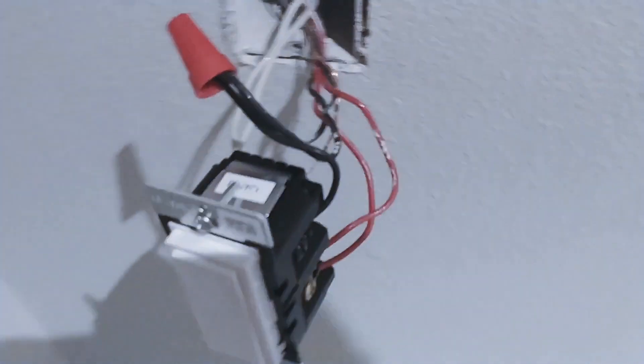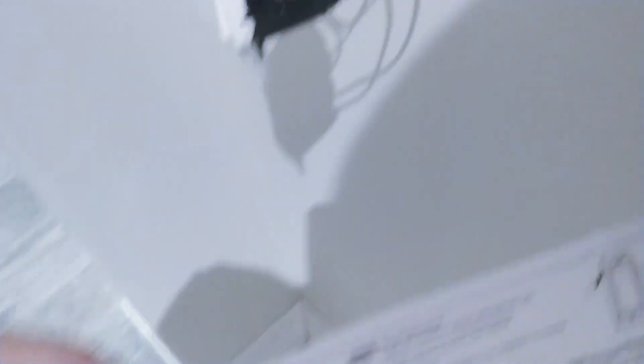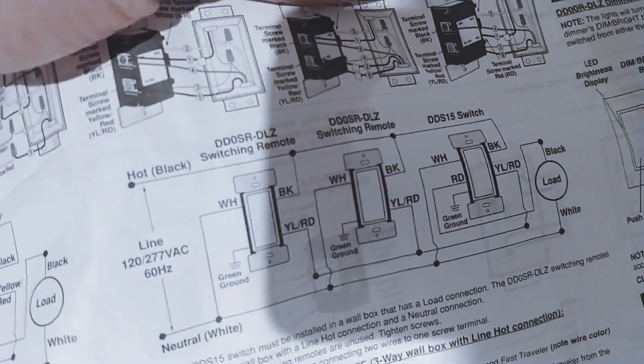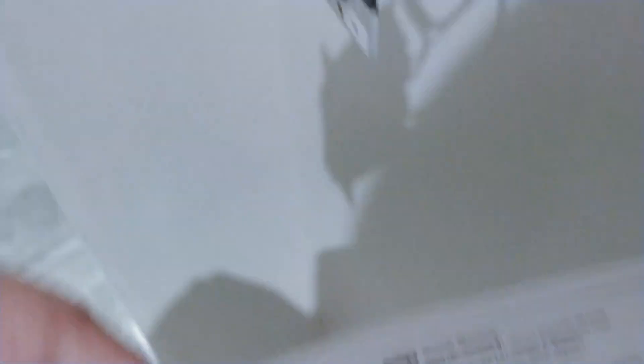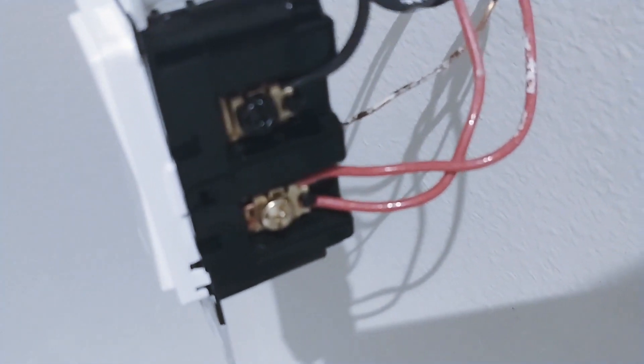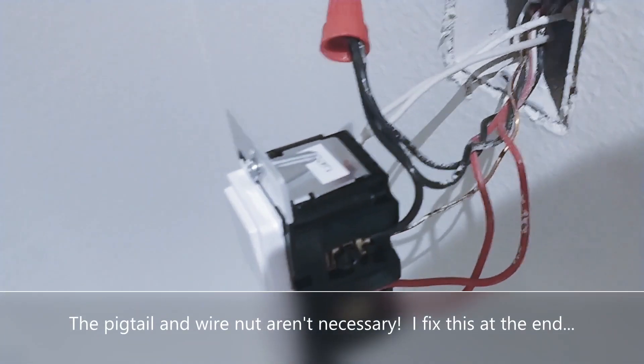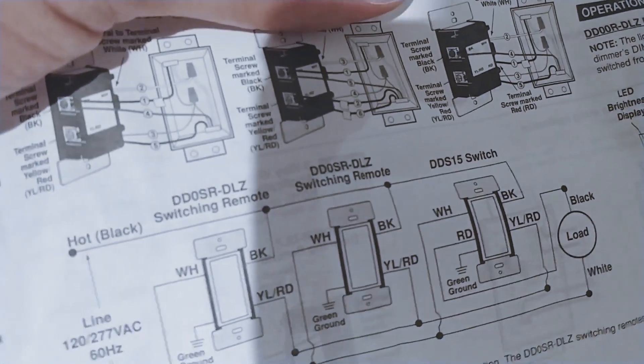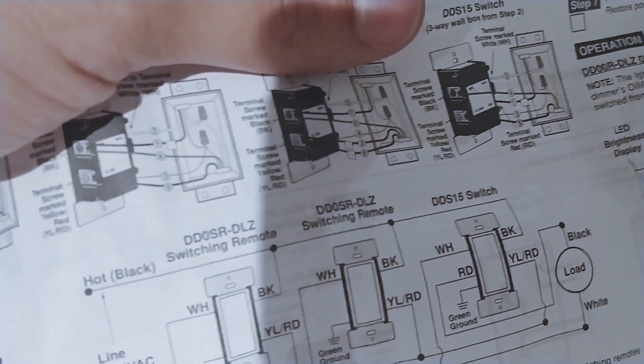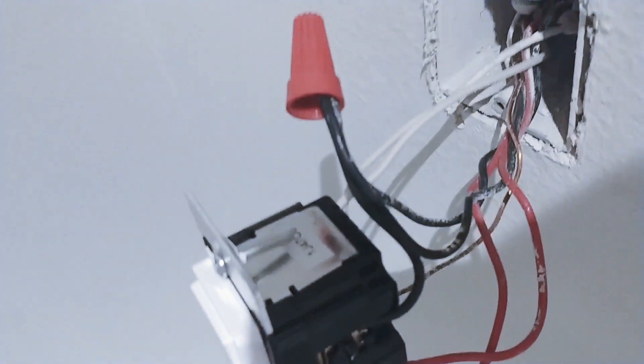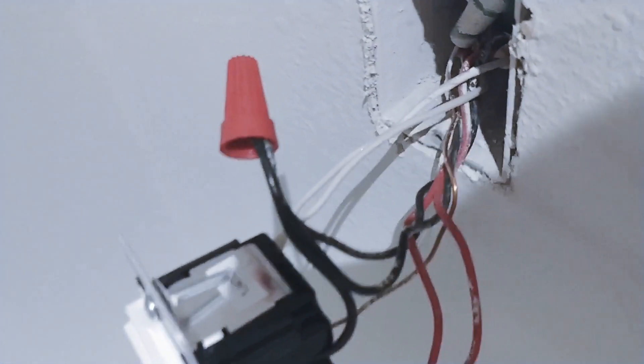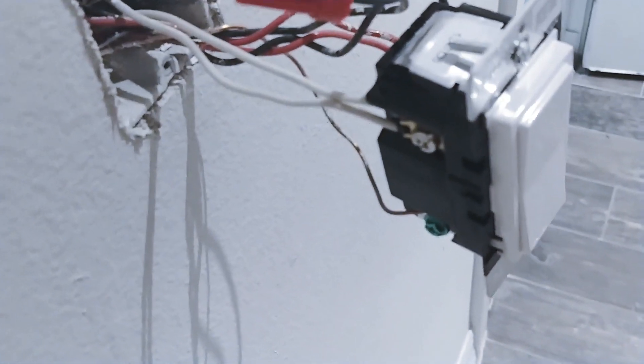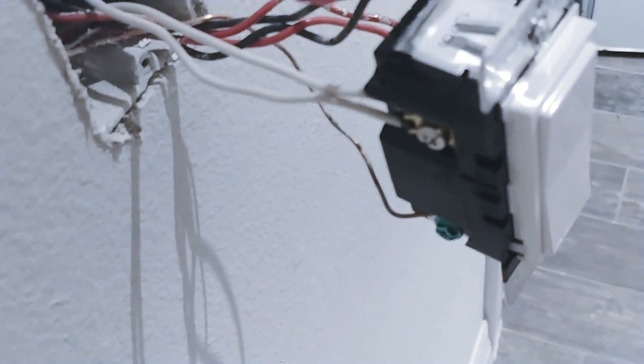Okay so here's where things get a little bit bizarre. This is the middle switch. What I did on here, you can see that the yellow and the red wire, they're tied together. So the two traveler wires are tied together by just being on the same terminal. The black wire is tied together with the switch behind it and the switch in front of it. So I took a jumper wire out of the black terminal and I wire nutted all black wires together. White wires are then jumpered together going into the same terminal and then there's the ground.